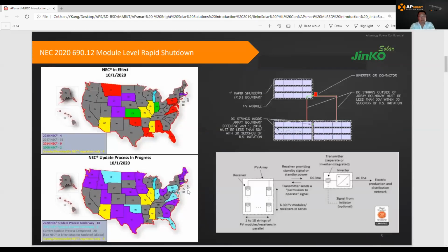Let me quickly introduce what the rapid shutdown requirement means. During 2014, the NEC posed their rapid shutdown requirement. Basically, they required that at the array level, outside the boundary, when the rapid shutdown is initiated, your voltage needs to drop below 30 volts within 30 seconds.